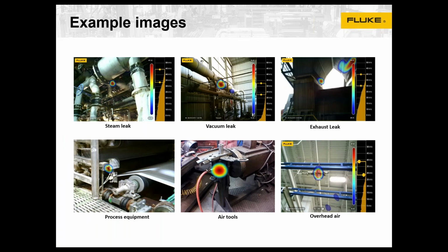Taking a look at a few example images in a variety of environments. Again, this technology works great, even in noisy environments. If you look over on the side here, you can see frequencies, and this is a noise level or dB level. You can see in this area, this exhaust leak is extremely noisy down in the audible range. But if you see the yellow box here, this effectively can ignore all of that noise and only map leaks, as evidenced here on the display, up in the ultrasonic range if you want.